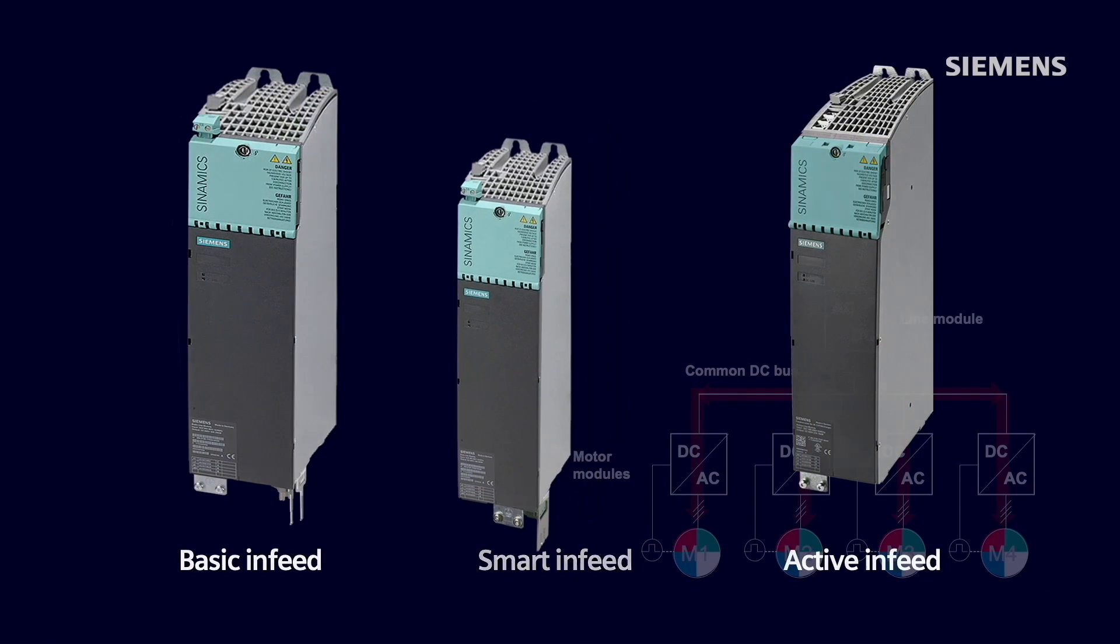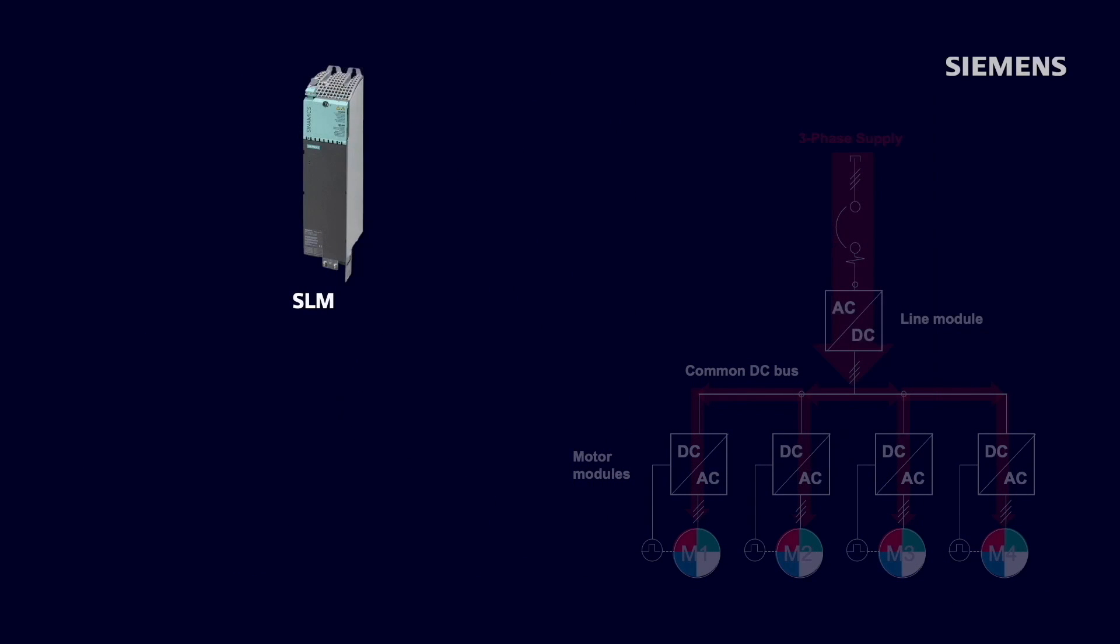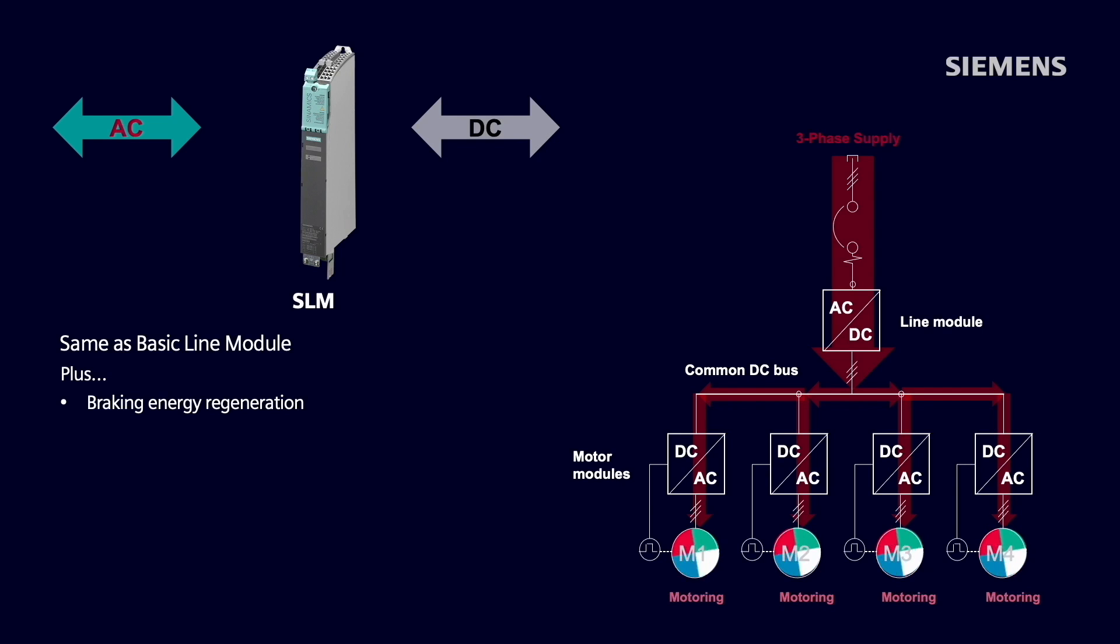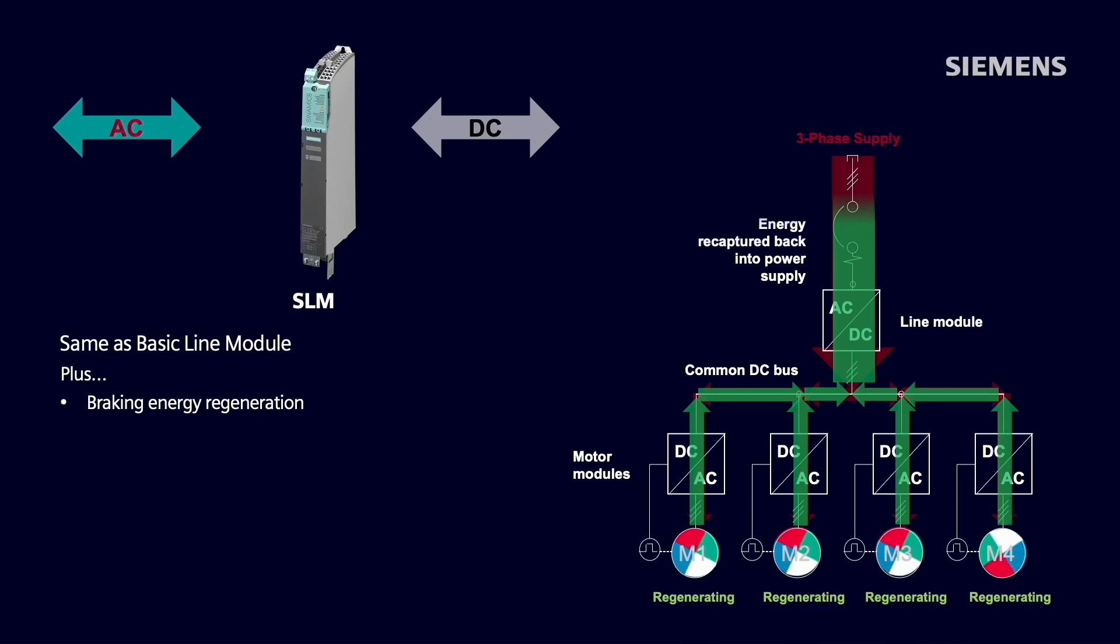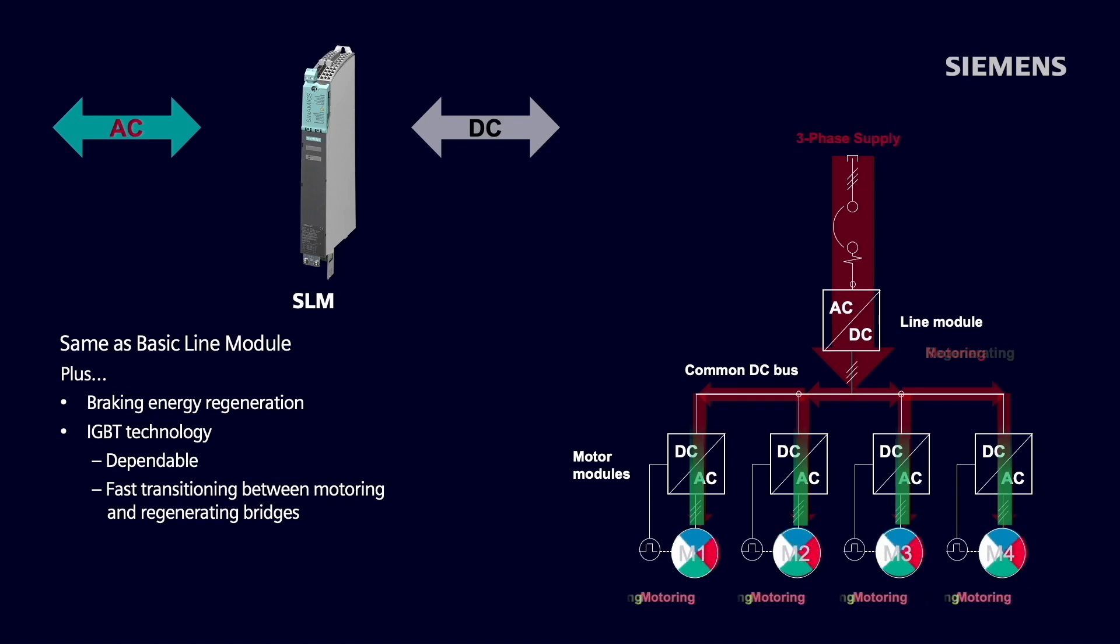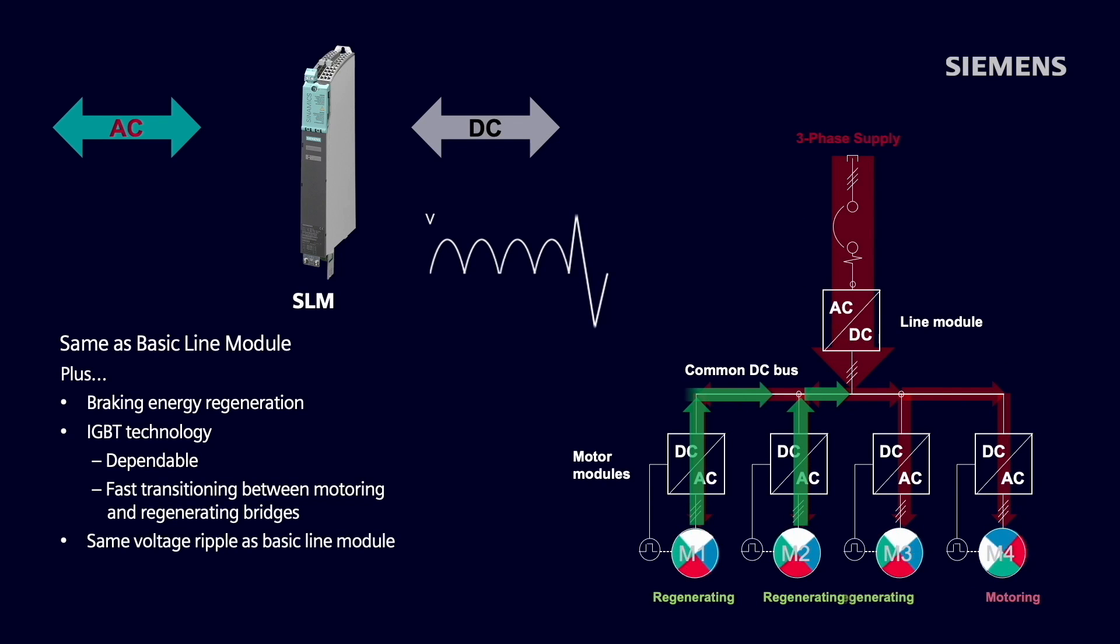Now, if we move to the middle selection in our flexible offering, we have the smart line module. The smart line module is regenerative, which means power can flow into and out of the line module, depending on the power differential between the three-phase AC supply and the DC link. So, anytime we have an overhauling load that increases the DC link, that power would be recovered back into the incoming line. This technology is controlled by IGBTs, which make this option very dependable and provides fast transitioning between the motoring and regenerating bridges. The DC link voltage and ripple with the smart line module is similar to the basic line module.